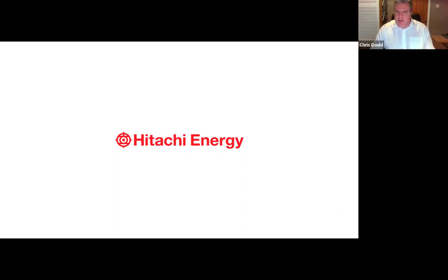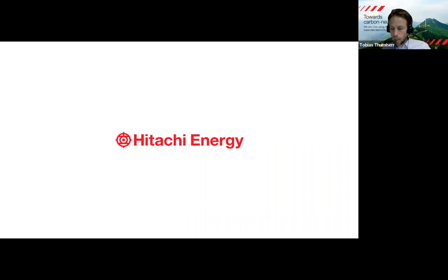If we move to the next question, I think it's Ray now. If the SFC has to come out of service, is a conventional backup supply provided? I think that's also a question of how the railway operator designs their power supply. It's common, it's required, to have some N-1 redundancy. So if one element feeding the railway network fails, there needs to be enough power to feed the railway system and to ensure normal traffic. And this can be done by having 2 SFCs per substation, or by having more substations than needed and allowing any of the substations to fail. So there are different concepts for that.